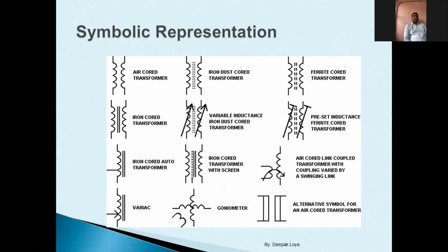Now, when you are an engineer, you will be dealing with SLDs. SLDs are nothing but symbolic representations, single line diagrams we call. So you may see various symbols for the transformers in the SLD. The transformers are represented by many such symbols, and each symbol has a different meaning. Whether it is an air core transformer or a variable voltage transformer, or a transformer with iron core, iron dust core, or ferrite core. So there are various symbols, and you must be aware of these symbols. Whenever you come across an SLD and the symbol is something different, then please recheck that symbol before taking any decision on that equipment.